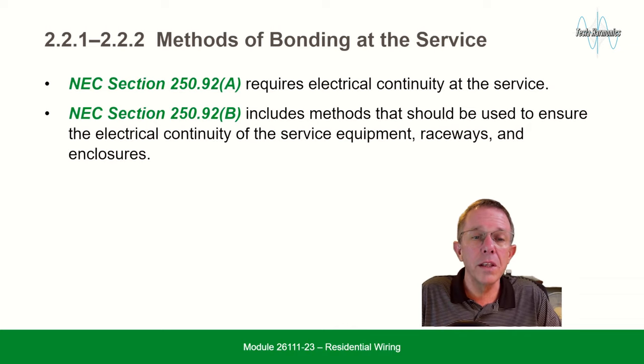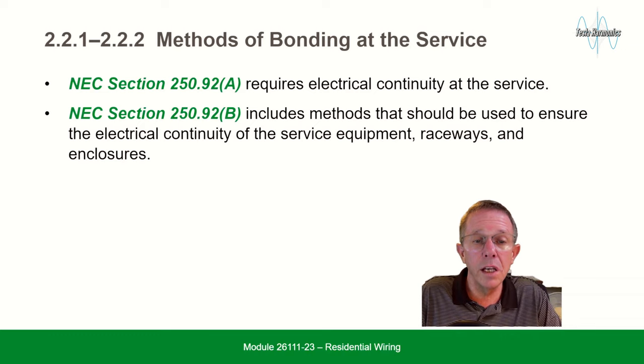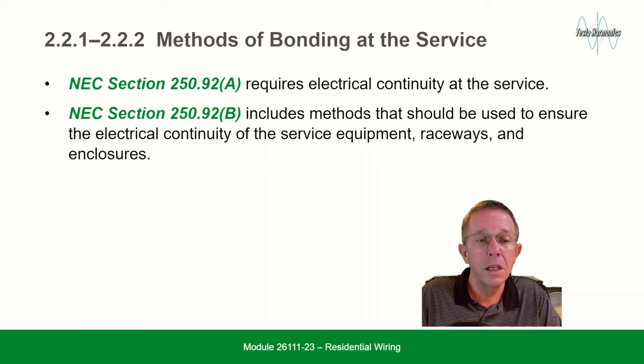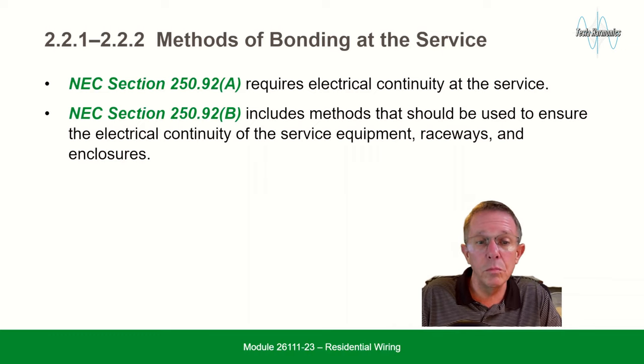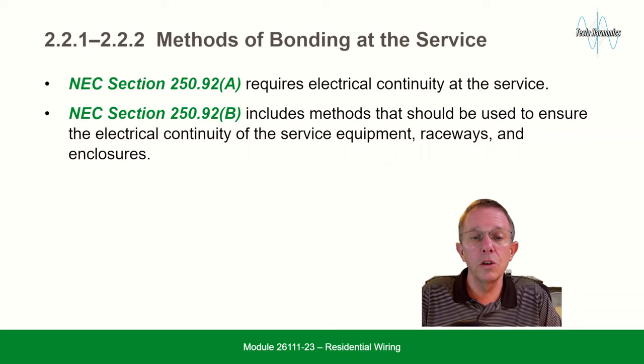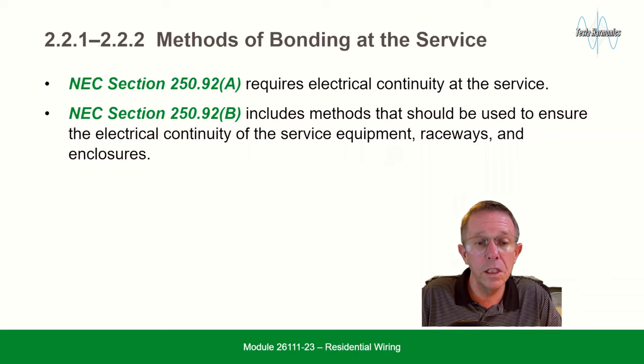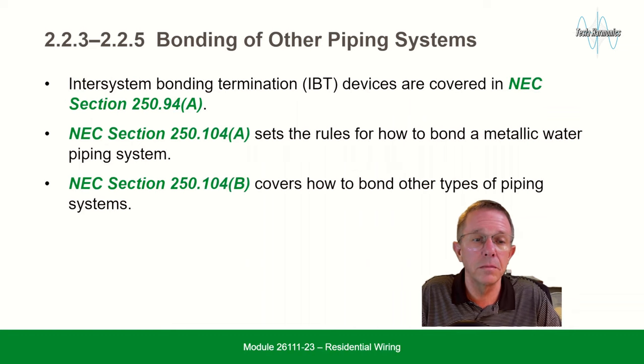Methods of bonding at the service: NEC section 250.92(A) requires electrical continuity at the service. NEC section 250.92(B) includes methods that should be used to ensure the electrical continuity of the service equipment, raceways, and enclosures.